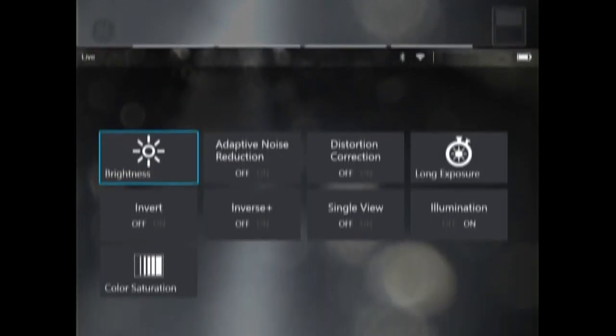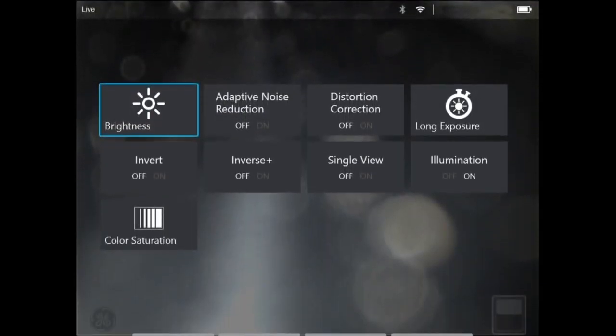And then in the middle picture there, we've also added these image transforms where you have the ability to adjust the screen brightness, adjust the camera gain and the light output of the camera. But you know that in some areas where the image is far away, it's big and dark, camera noise will get massively snowy on the image, and the adaptive noise reduction will take that snow out of an over-gained processor or video circuit.